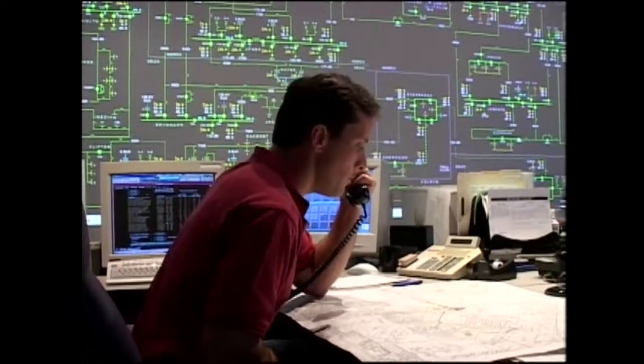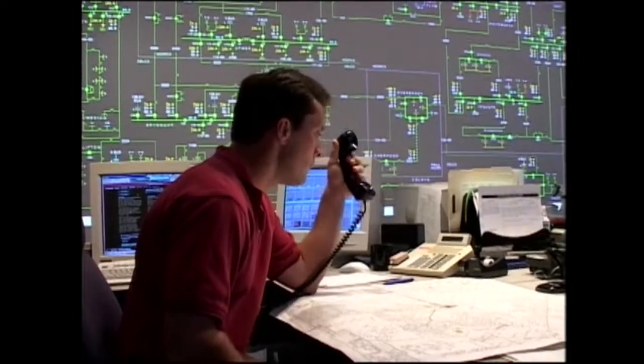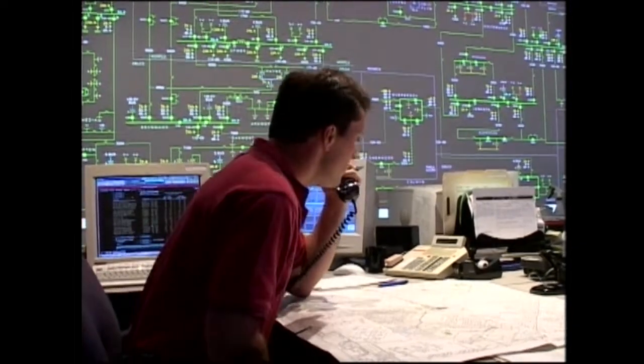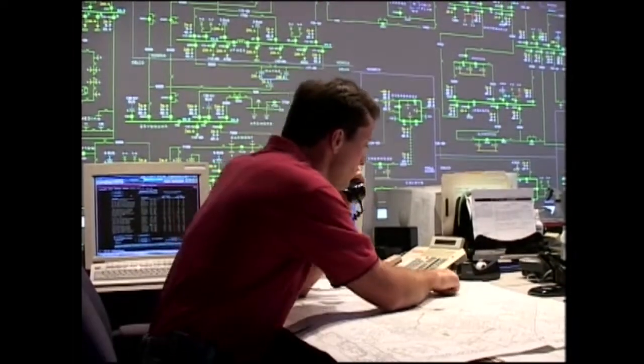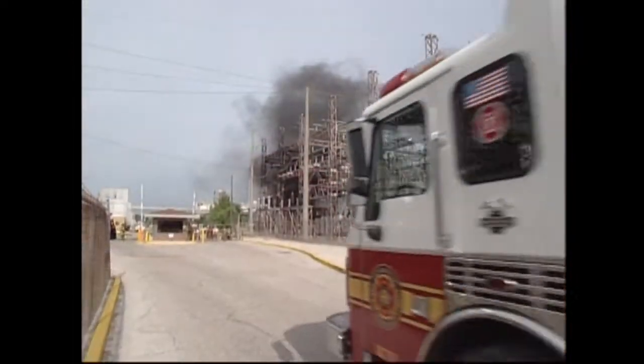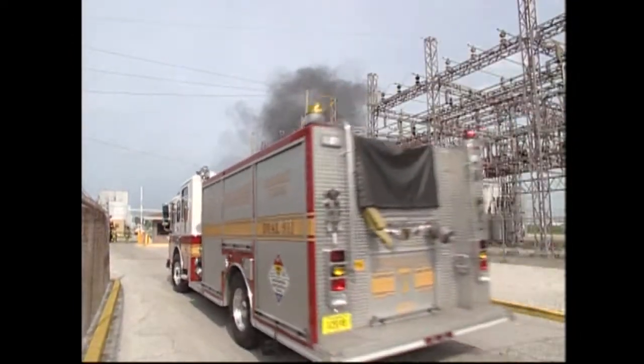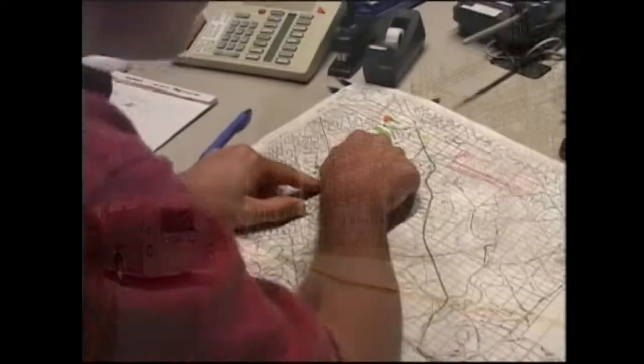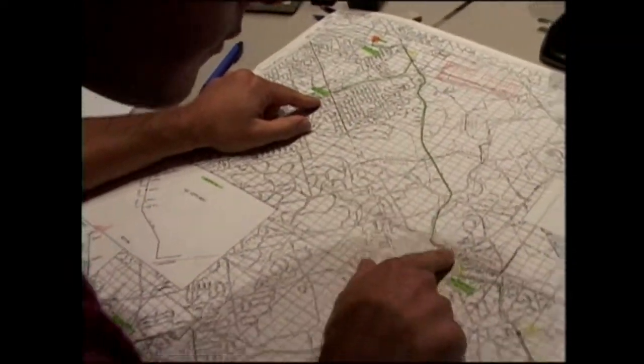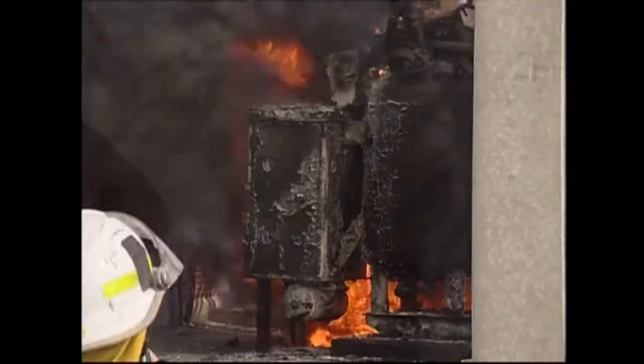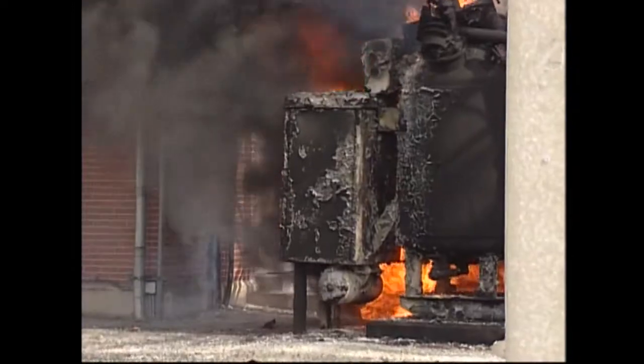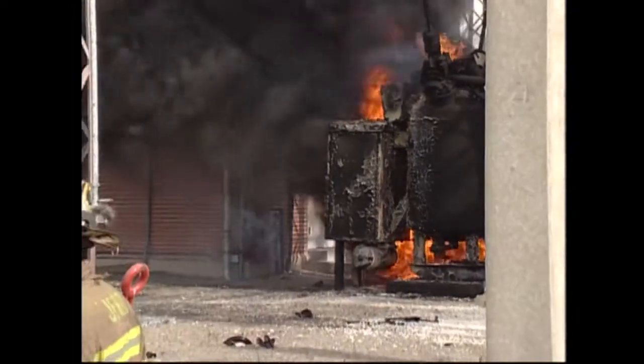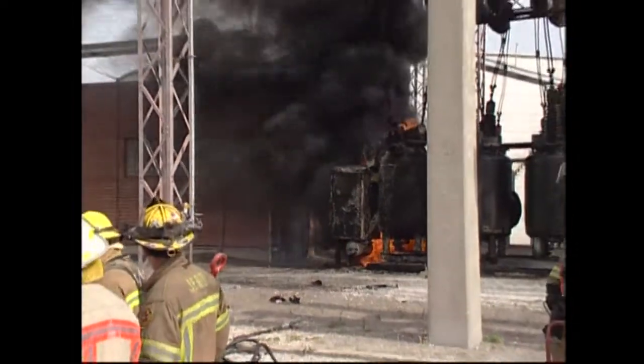The utility company control center will most likely be aware of a problem at a substation and immediately dispatch personnel to the site. However, you may be on site first, and if so, be sure to call the utility company just to make sure that they're aware of the emergency. Under no circumstances should you attempt to enter the substation before the utility company experts are on the scene.